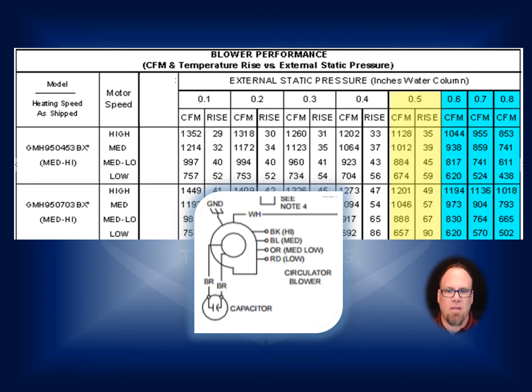Is that going to be good for every application? Do you just not set it up after that and don't need to check it because the manufacturer knows what they're doing? Well, no, that's not the case at all. That is a very specific setup that's there for the manufacturer, and the days of leaving it the way the manufacturer has it, those are gone by the wayside. So you have to check it. You have to put your static pressure tubes in there, and you have to check everything. So you check before the blower and you check after the blower. And once you check before and after the blower, then you make your assessments.